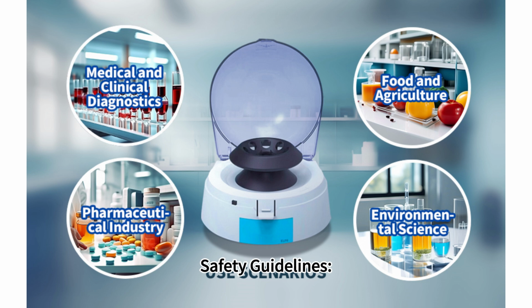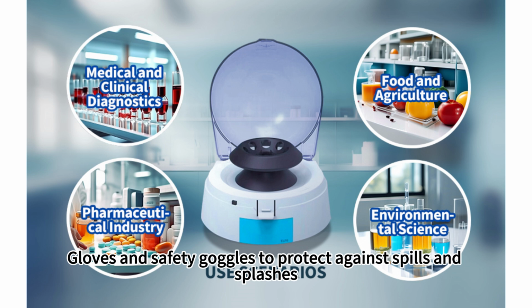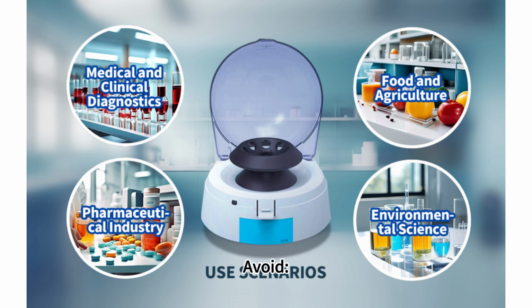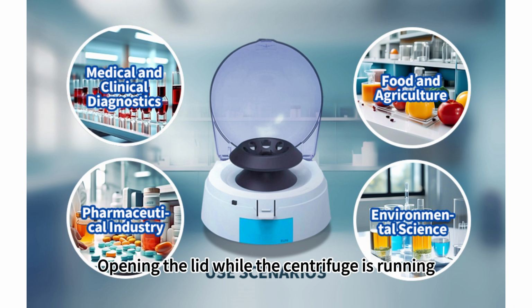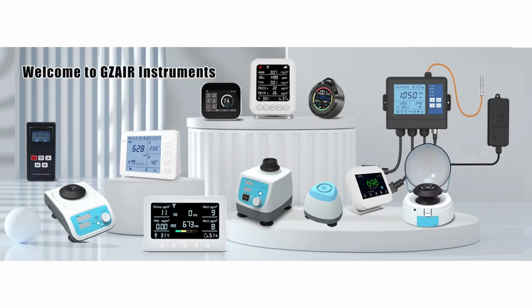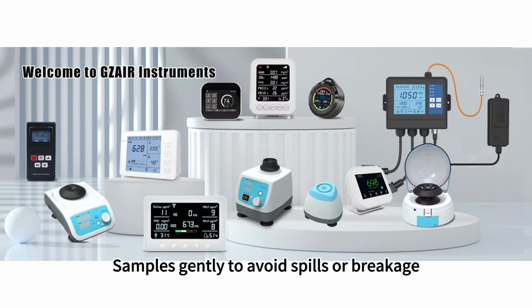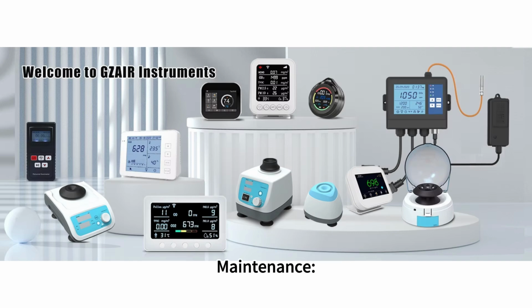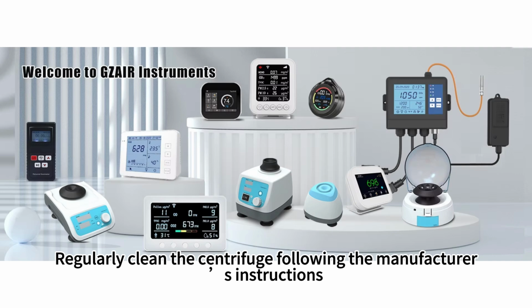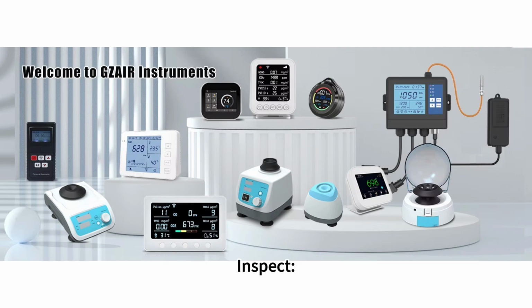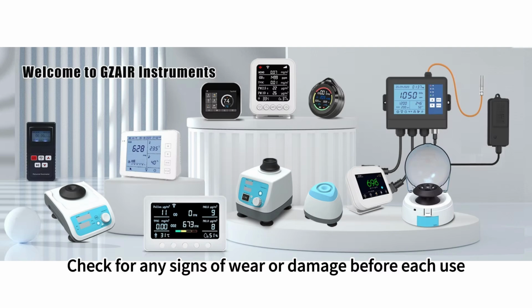Safety guidelines. Personal protection. Wear gloves and safety goggles to protect against spills and splashes. Handling samples. Avoid opening the lid while the centrifuge is running. Handle samples gently to avoid spills or breakage. Maintenance. Clean. Regularly clean the centrifuge following the manufacturer's instructions. Inspect. Check for any signs of wear or damage before each use.